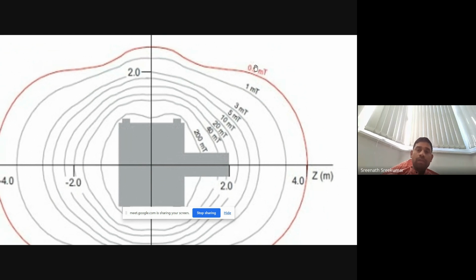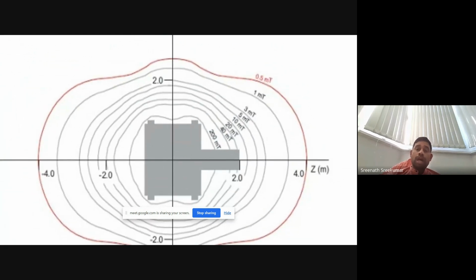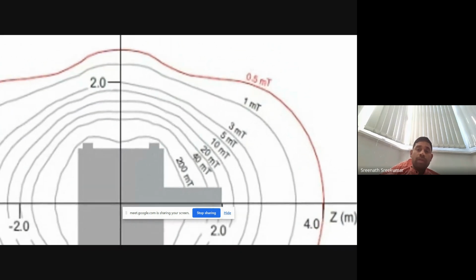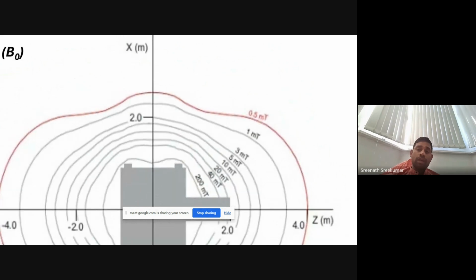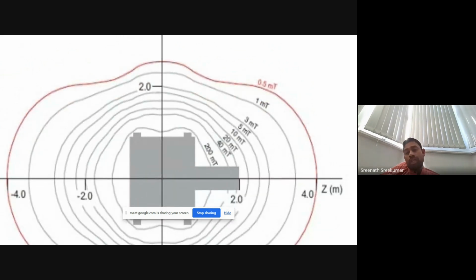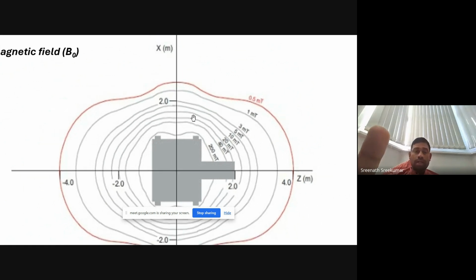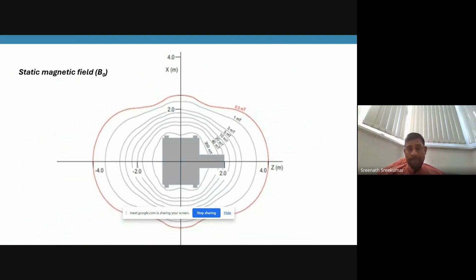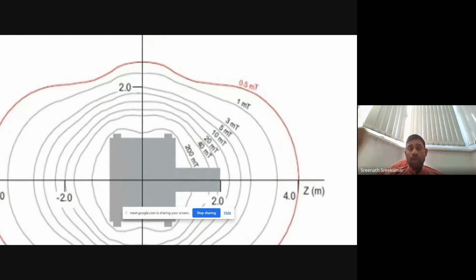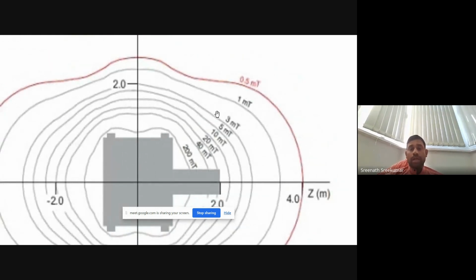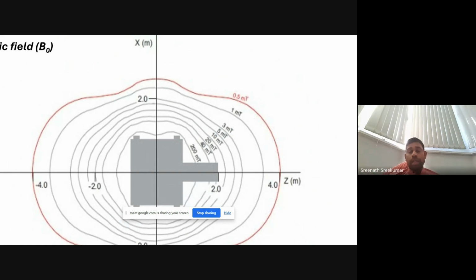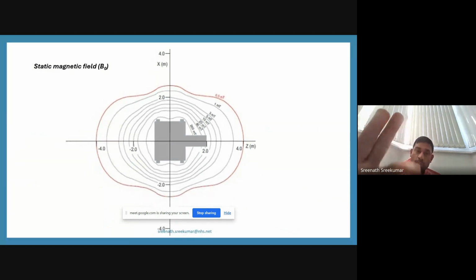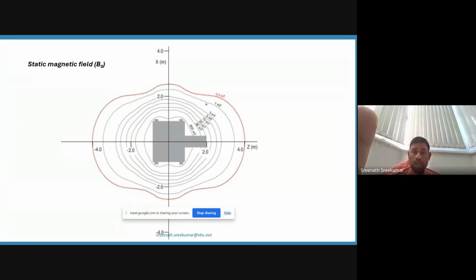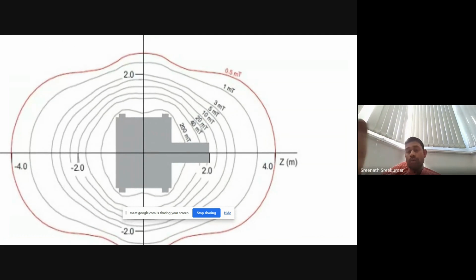Any active devices are not allowed above this level. If you go within that range, it can cause hazard to the personnel or the equipment. So I just want you to clearly understand how the spatial gradient is distributed inside a scanner. If you're going to the MRI scanner, you should have this picture in your mind, and this should make it easy to understand the safety standards.